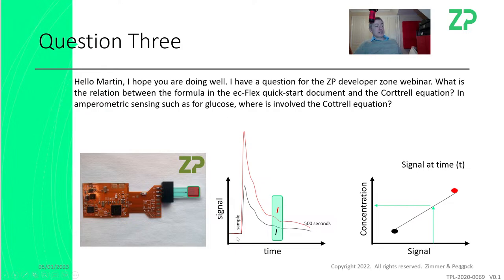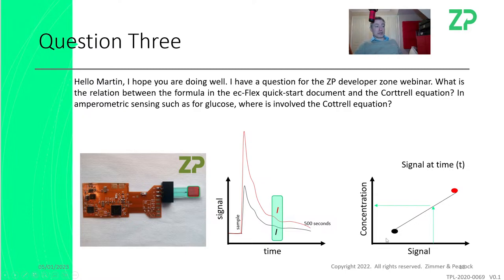They choose five seconds because their assay is very soluble — it solubilizes into the sample quickly, and a diabetic doesn't want to wait more than five seconds. So they optimize for both: is my signal strong enough, and will the customer wait that long? In the factory, they make a batch of electrodes, calibrate some of them, and produce a batch calibration. That calibration is then shipped with the product so that when used on an unknown sample, the device looks up the signal against the calibration curve to reveal concentration.